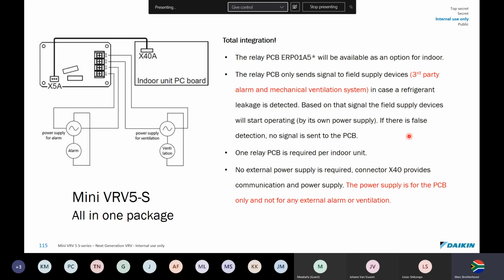So instead of using iTouch Manager and all the more expensive stuff, you can just order this board, and if there's a leak on that indoor unit, based on that signal, the field supply devices will start operating by their own power supply. If there's a false detection, no signal is sent. So it's pretty much a third-party information PC board. The downside is you need one relay PC board per indoor unit. Okay, and there is also no external power supply required.